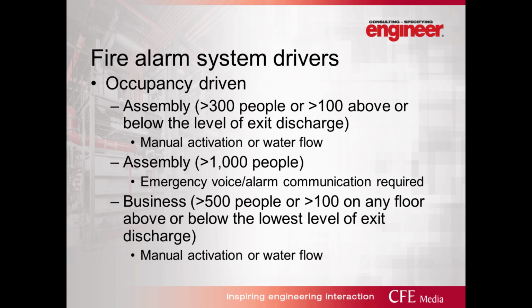Now, typically when we are having a sprinkler system installed in the building, codes would require that system to be monitored for activation. And it's usually required, the IBC would require either central, remote, or a proprietary supervising station to monitor those systems. But if we have a fire alarm requirement, that sprinkler system water flow activation would also notify the occupants. Now you can see with assembly occupancies where we have an occupant load of greater than 1,000 people, we would have an emergency voice alarm system. So, when the code says an alarm system, it's not necessarily requiring voice. It could be requiring just sounders and strobes, right? When we have a voice alarm system, we're required to be able to provide a voice message. And we also would be providing visual devices or strobes to notify hearing impaired occupants.